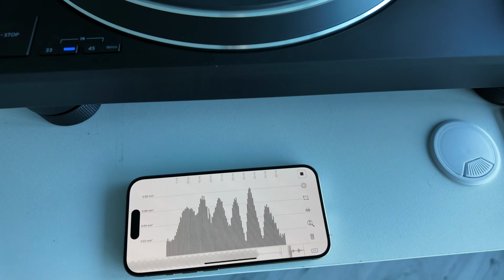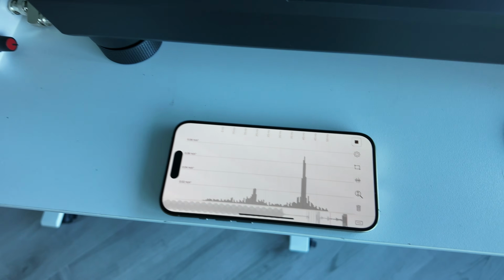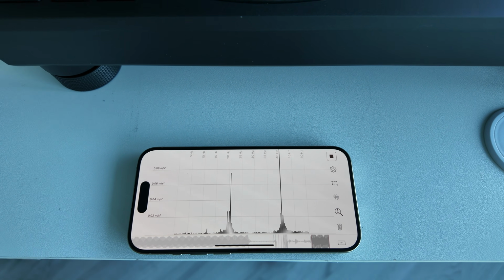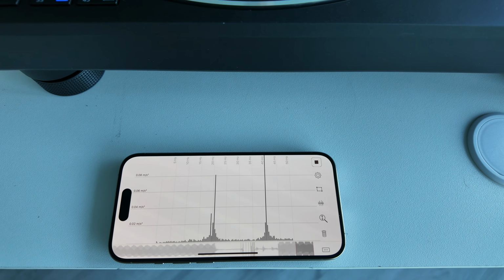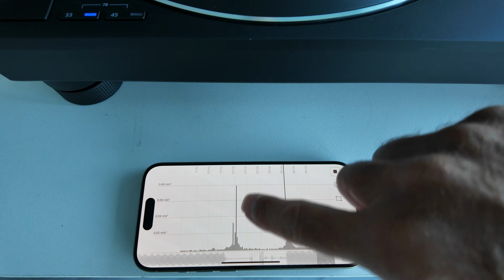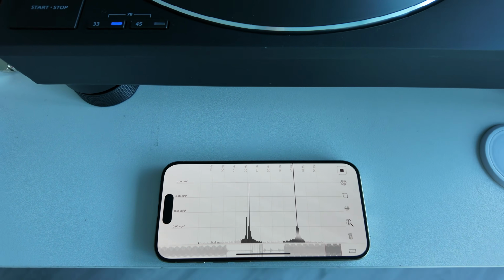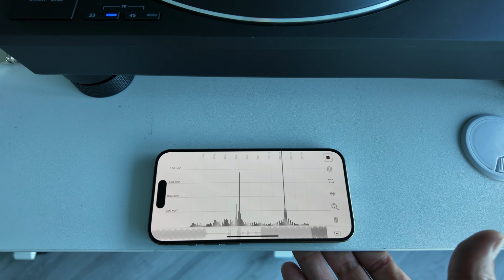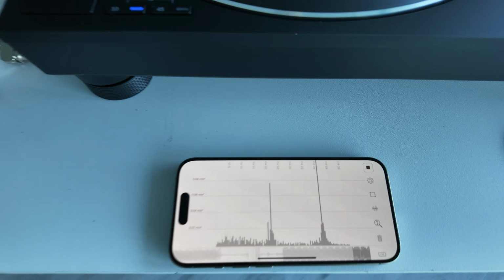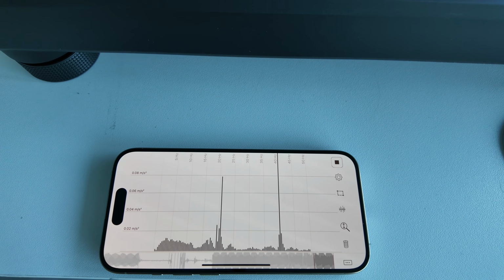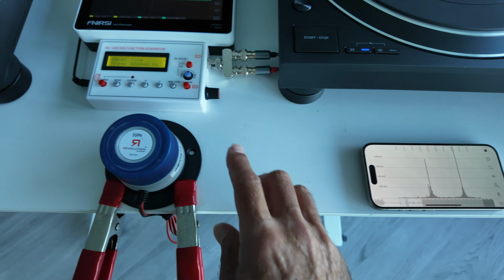If I measure the same thing on this other side, turn on the generator. Once it settles down, it's just about the same thing. So we've got a little bit of a 20 hertz resonant frequency here, which is very common. And if I play with the table, I can get that to be a little bit off, but essentially the amplitude is the same for both here.